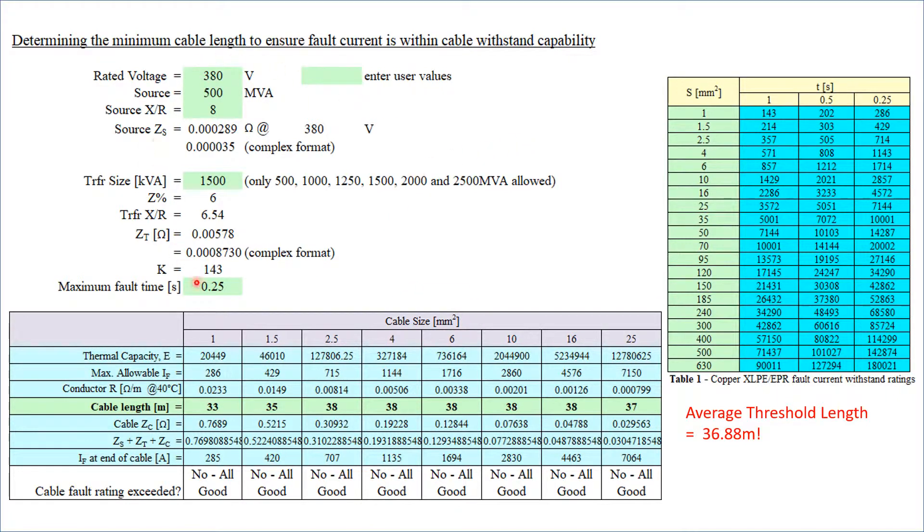So looking at this again, I can now increase my cable length to see how much cable length do I require in order for my fault current at the end of the cable to be less than the actual cable rating, the withstand rating of my cable. I see for a 1 mm² cable, for example, I will need 33 meters. For 1.5, I need 35. For 2.5, I need 38, and so on. So my average threshold length, the TL, is 36.88 meters.